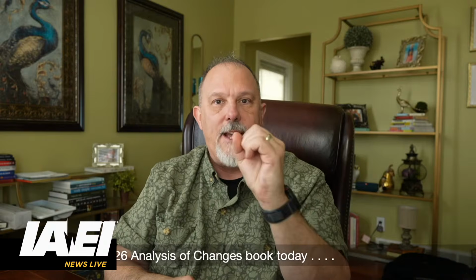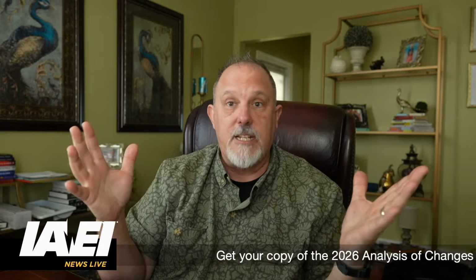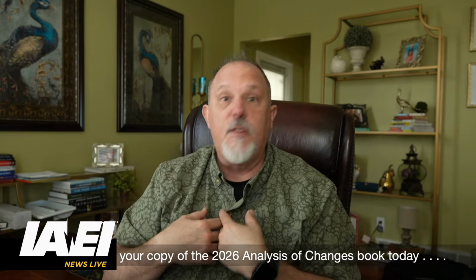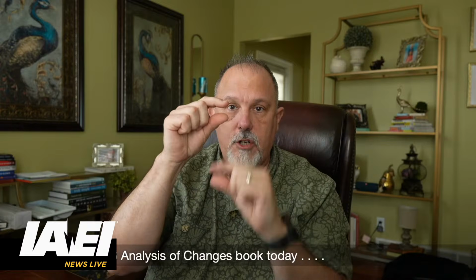We said the raceway has to be encased in at least 2 inches of concrete. It doesn't say anything about the size of the raceway. It doesn't say how much needs to be on top or bottom. It just says it has to be encased. So I would think that if I only had a 1/4 inch and 1/4 inch and I had 2 inches of concrete, I would say I met the code requirement. Show me how I'm wrong.